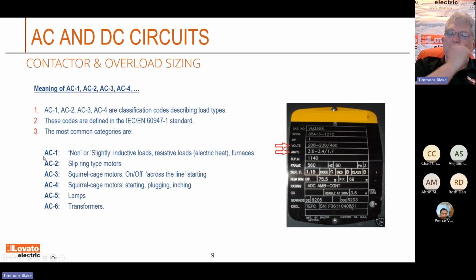And you also have to realize when you're dealing with motors or you're dealing with current for the contactors, you got to know what category it is. And most every time our contactors are sized for the AC3 category. You can look up current categorizations on Wikipedia, and you'll see these AC categories for AC motors. And AC3 is typical. It's a squirrel cage motor for starting and stopping. But sometimes you'll get an AC1 rating. Sometimes people will only use these contactors for resistive loads, for heating elements, and maybe some incandescent lights. All right. So there's these different current categories you got to be aware of. Okay.